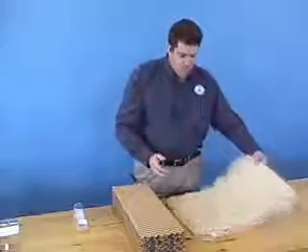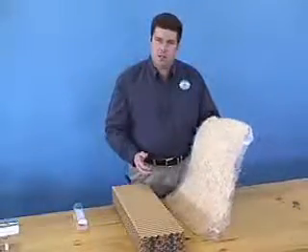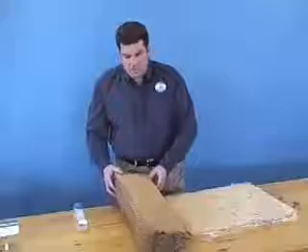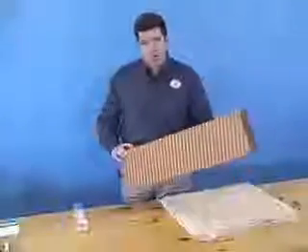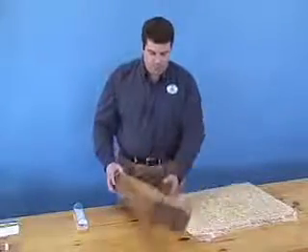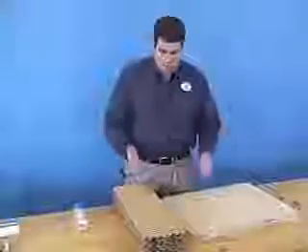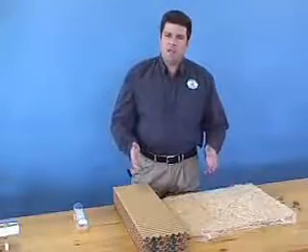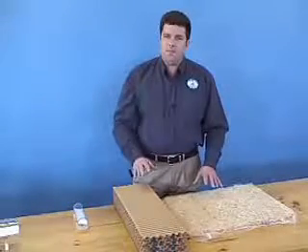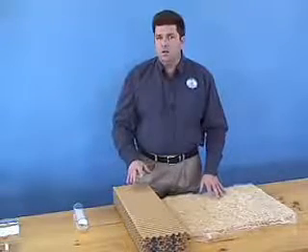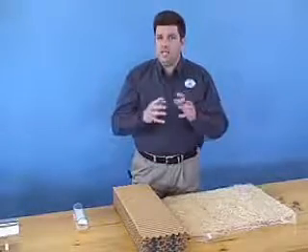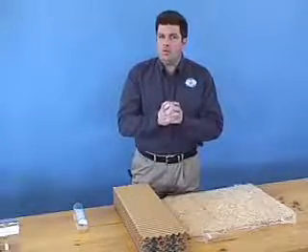Aspen pad swamp coolers can reach about 70% of the wet bulb temperature from their starting point. Corrugated cardboard type swamp coolers are better at swamping the air, and they can reach about 90% of the wet bulb temperature. These types of mechanisms are called direct evaporative coolers because they add moisture directly to the air that enters the building. Direct evaporative cooling is adiabatic cooling, which means no heat energy is removed from the airstream. The heat is simply hidden in the water molecule in the air.